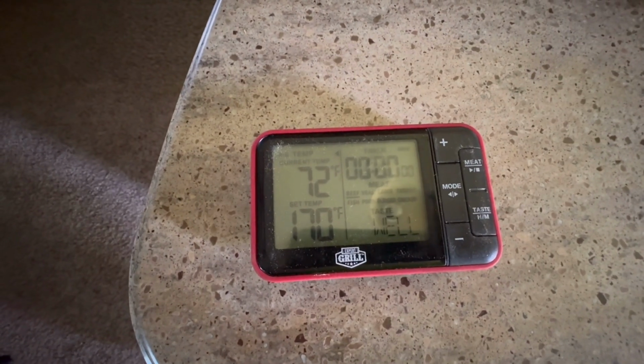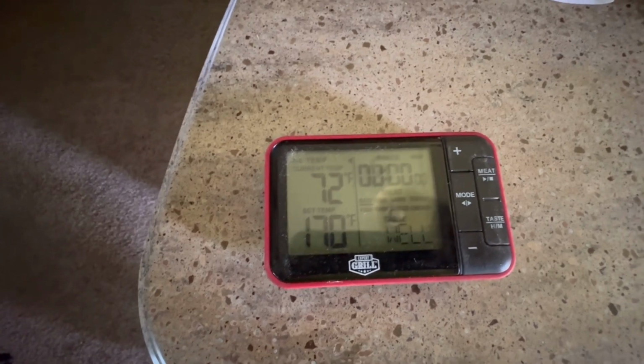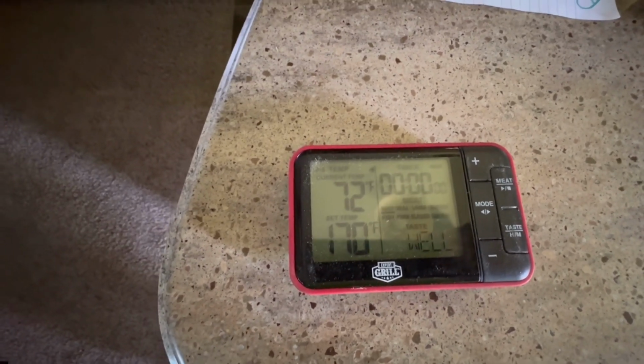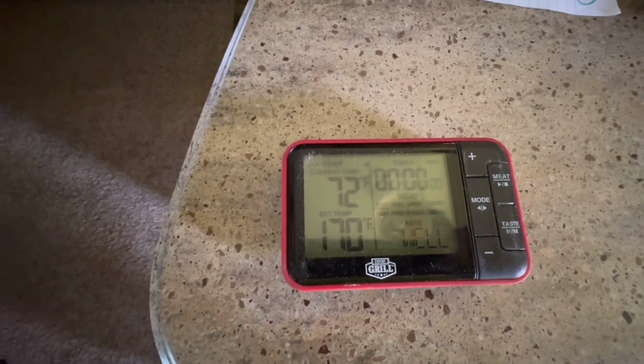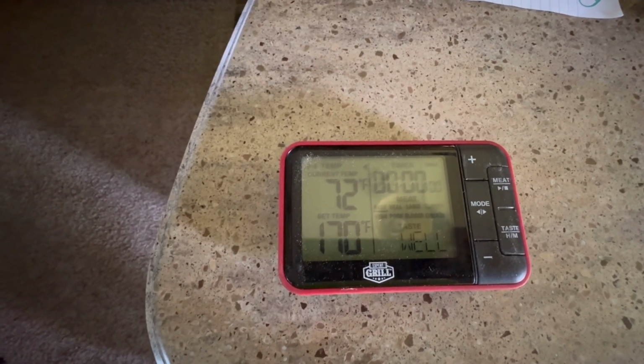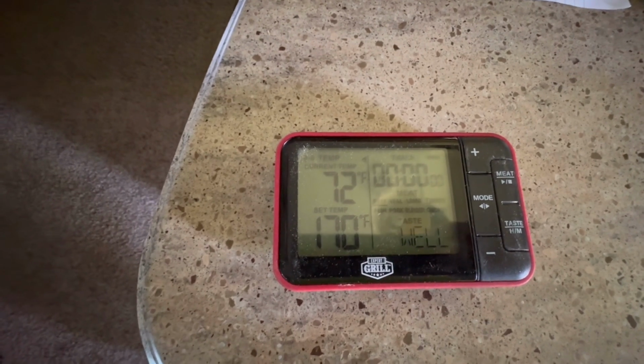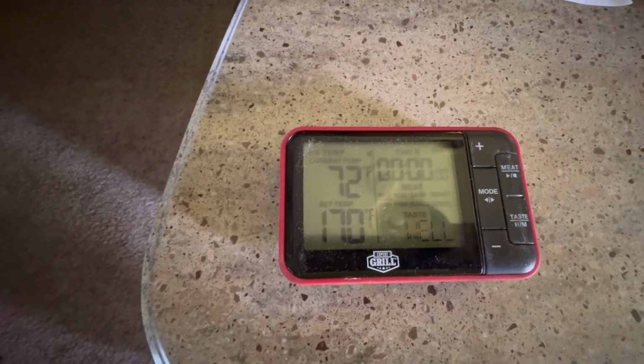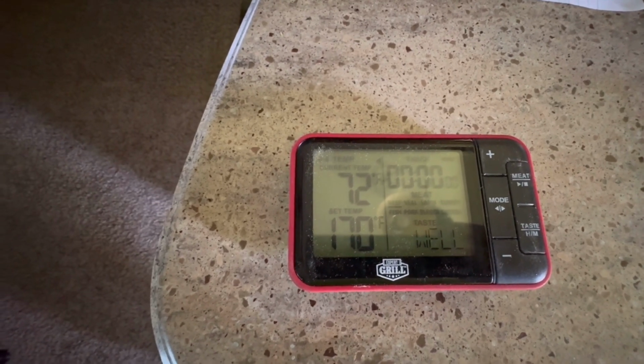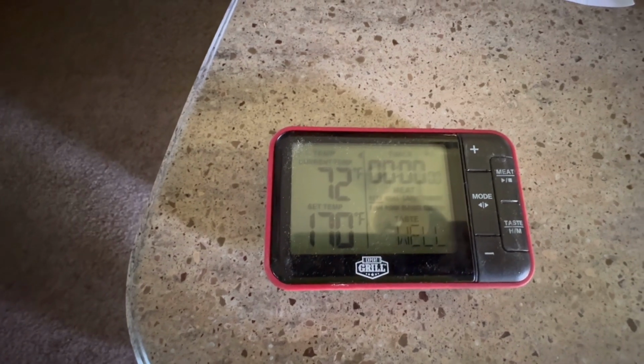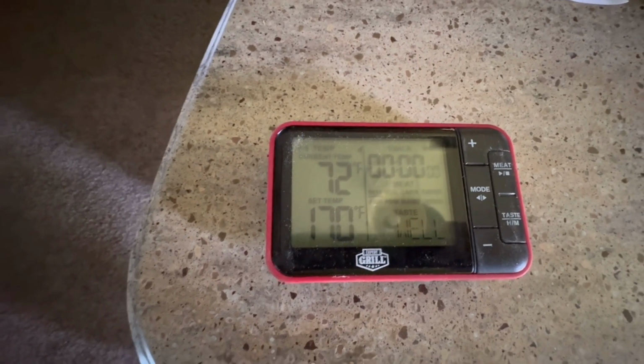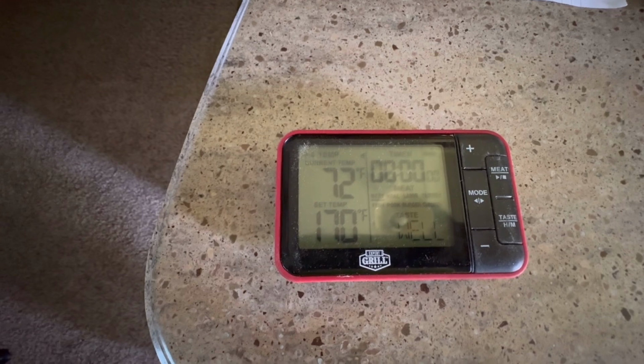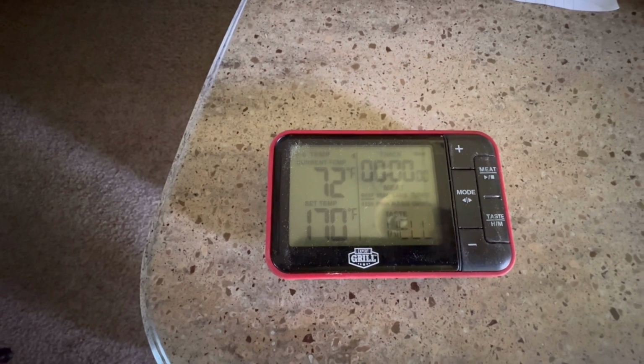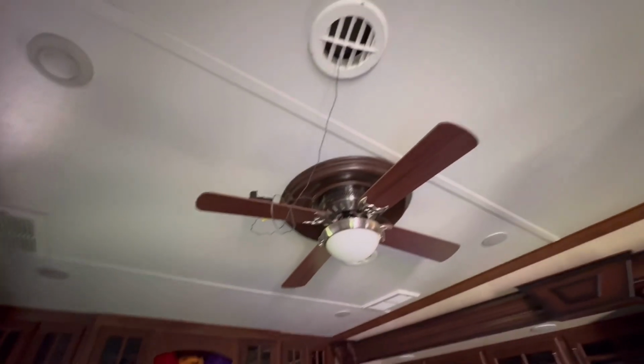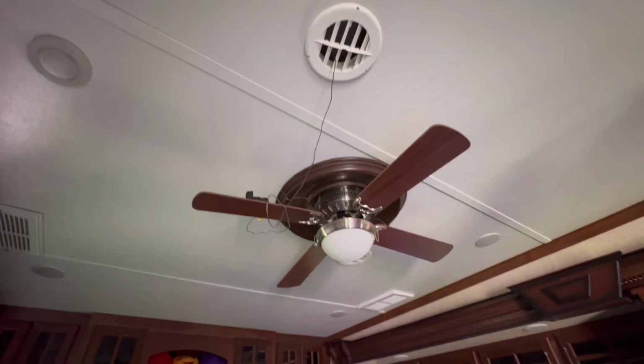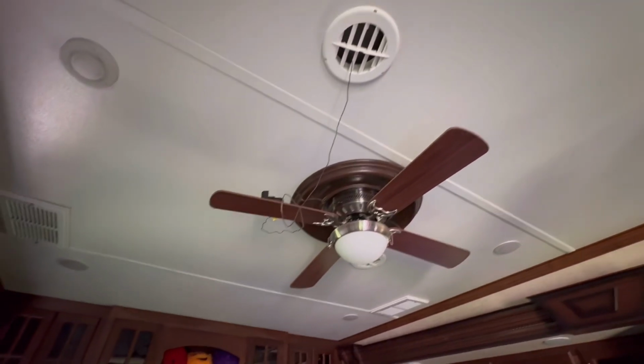Okay, now what we're going to do is check the return air temperature versus the overhead duct output air temperature, and we're going to expect to see somewhere in the neighborhood of 18 to 22 degrees difference between the return temperature and the overhead duct output temperature. So you can see right now we show 72 degrees on the return duct inside. Again, the AC's been running maybe 3 or 4 minutes. And now we're going to measure what the actual temperature is coming out of one of these overhead ducts.